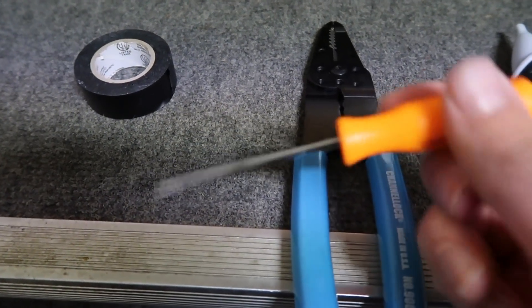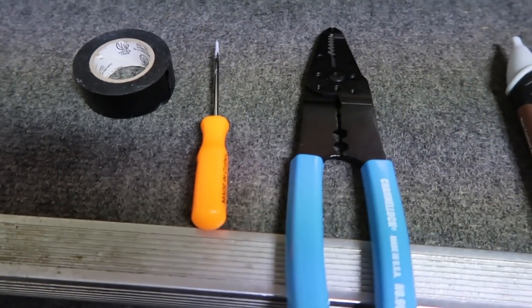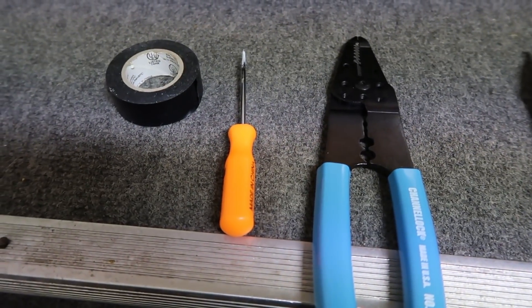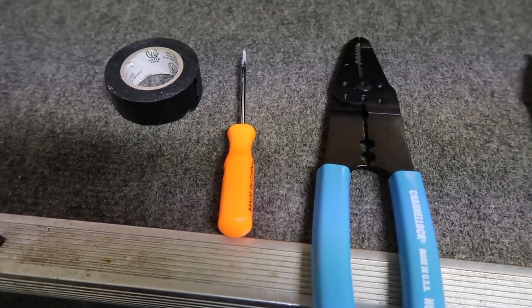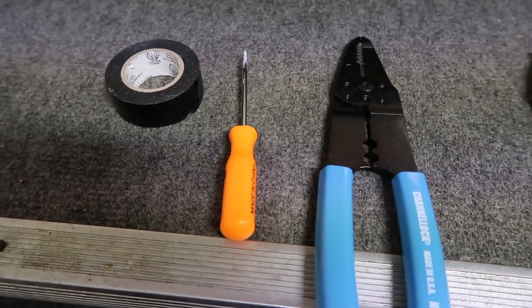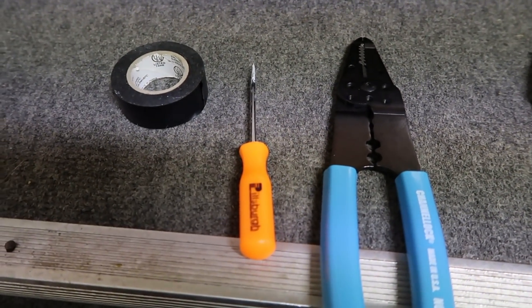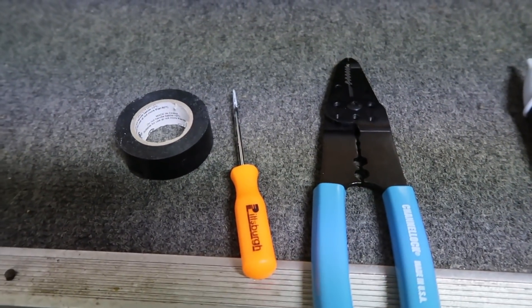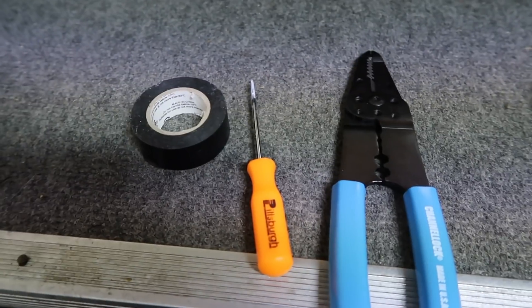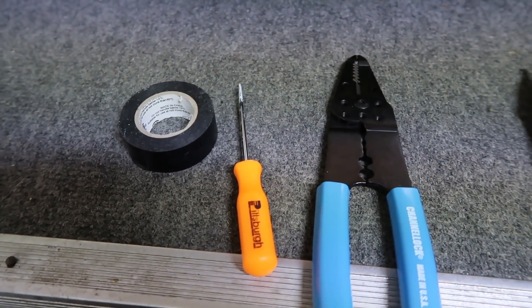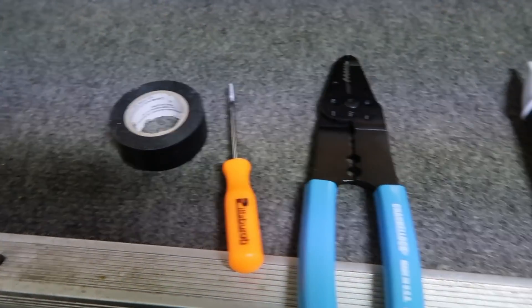And then also, lastly, I recommend a pick, sharp pick. You may not need this. You would only need this if the outlet has been stabbed in the back by the actual wire. You would need this to press in and release that wire. And then, lastly, I recommend some electrical tape. And I'll show you what I use that for. I tape up the outlet on the inside so that way the ground wire doesn't touch on any of the terminals.